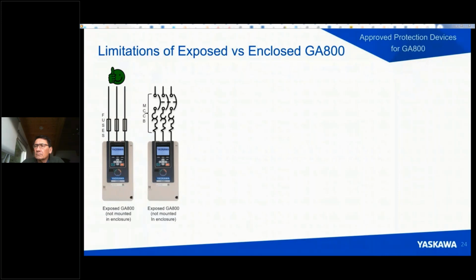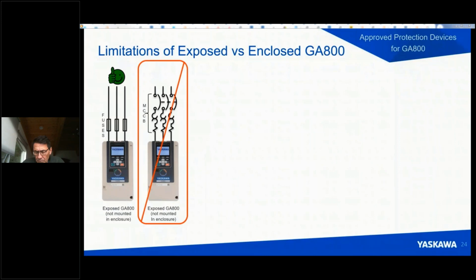When we try to protect that exposed drive, not mounted in another enclosure, with just a molded case circuit breaker, this does not work when it comes to something that needs to be UL listed. Okay, and does something need to be UL listed or not? Yes, it does. According to the NEC, it has to be listed with another agency. And then, of course, if it's listed, it has to be used per the instructions. So this kind of scenario no longer works.